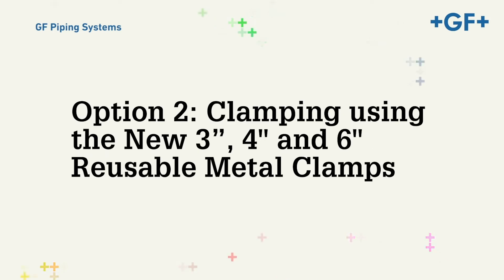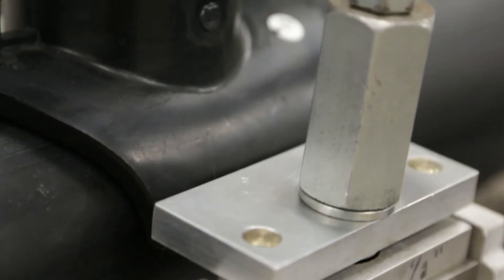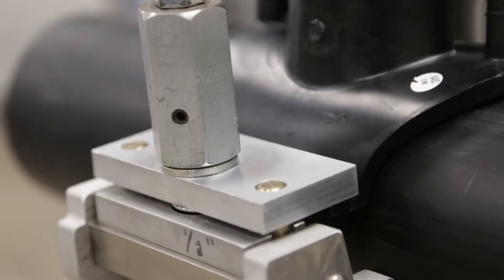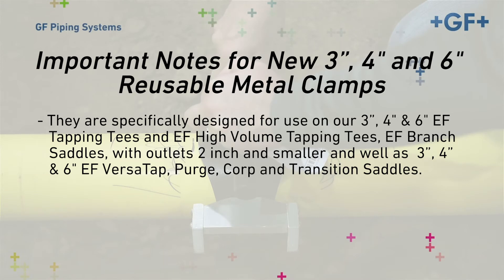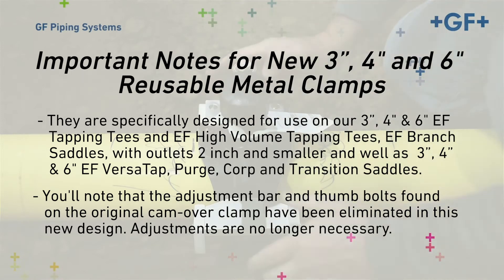Option number two: clamping using the new 3-inch, 4-inch, and 6-inch reusable metal clamps. These clamps represent the newest product improvement in Georg Fischer's Central Plastics line of reusable metal underclamps. They are specifically designed for use on 3-inch, 4-inch, and 6-inch EF tapping tees and EF high-volume tapping tees, EF branch saddles with outlets 2-inch and smaller, as well as 3-inch, 4-inch, and 6-inch EF VersaTap, Purge, Corp, and transition saddles. The adjustment bar and thumb bolts found on the original camover clamp have been eliminated in this new design.